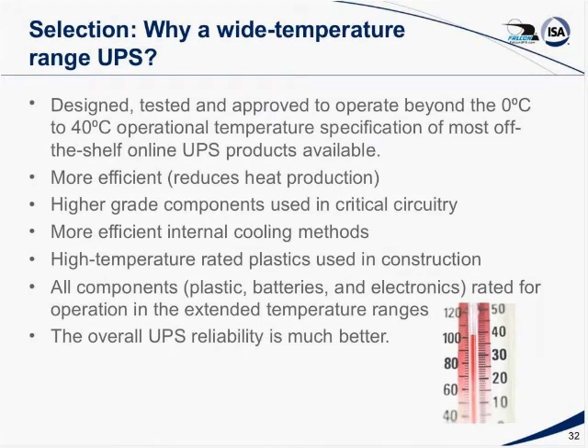Okay, Larry, could you go through a little bit about selection of a wide temperature UPS? Well, yes, a wide temperature range UPS is designed, tested, and approved to operate beyond that standard 0 to 40 degrees C operational temperature that most of your off-the-shelf UPSs have. They're designed this way because, first of all, the efficiencies are designed in to reduce internal heat production. They use the higher grade components Mike spoke of in the critical circuitry, so heat does not affect these components. They certainly have different and more efficient cooling methods. They use much higher rated temperature plastics in the construction, and everything that's in there, if it's done correctly and designed correctly, is rated for operation in the extended temperature range. This makes the overall UPS reliability that much better. And remember, reliability has to be designed in. It can't be added on.